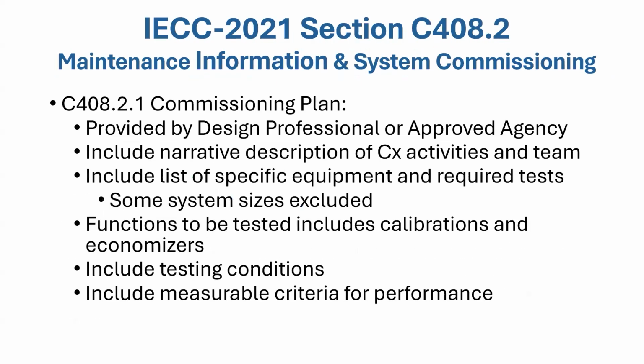Next. Maintenance information - here we're talking about the commissioning or verification plan, 408.2.1, provided by the design professional or approved agency. They want a narrative description: how is this stuff supposed to work, what are the verification or commissioning activities, what are they supposed to do. It's not just one person - it includes a list of equipment, what's supposed to be tested, what it's supposed to do, and what criteria it must meet. This includes calibrations, economizers, and all kinds of other things covered in 408.2 and testing conditions.